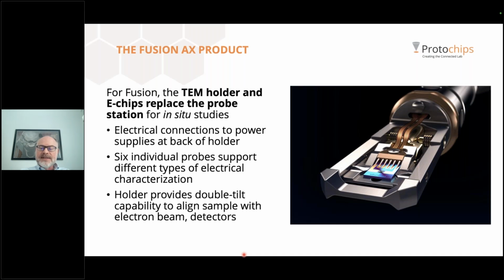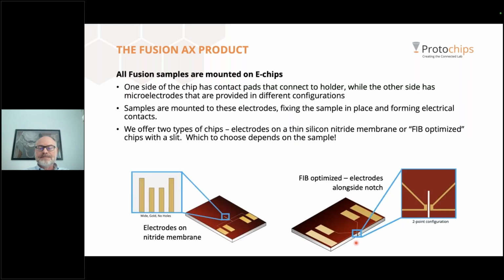Those connections run down the holder to the tip, where, as shown here, we have 6 individual probes that will land on a chip. And we call these chips E-chips, as Zayna said. The 6 probes there can support different types of analysis or sometimes even multiple samples. Your sample goes on the E-chip. Finally, the holder, as Zayna mentioned, also has a tilt capability so that you can get your sample into specific orientations or angle it towards different detectors that the microscope has.